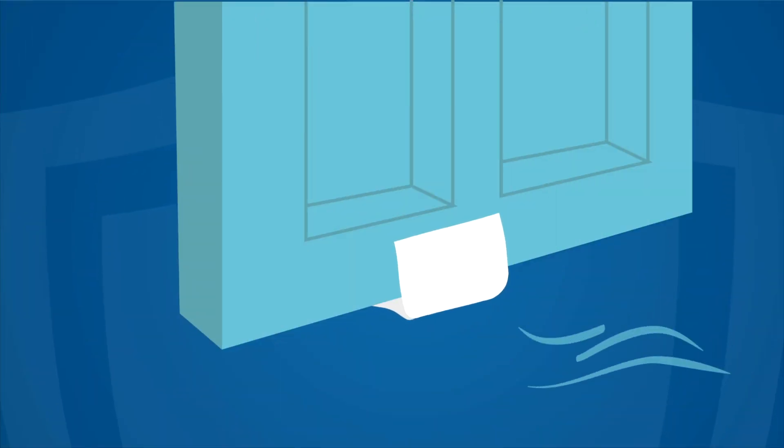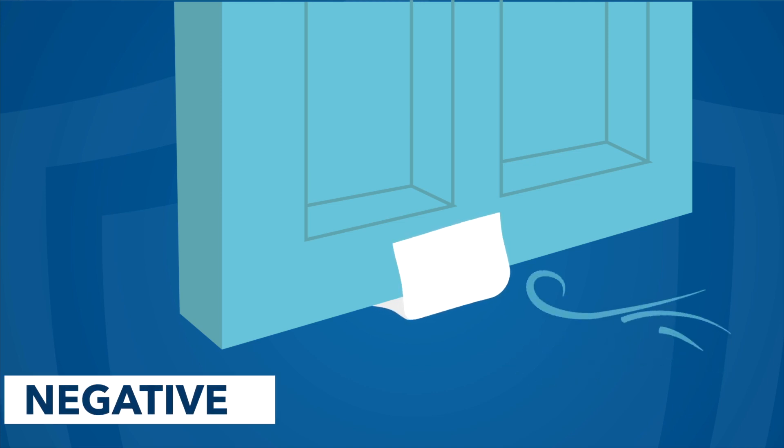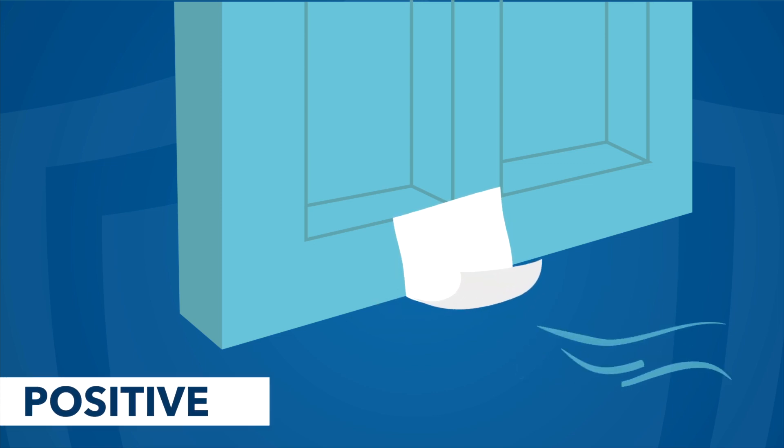If you are concerned about a room's pressure, you can quickly check to see if a room is positive or negative pressure by holding a tissue or piece of toilet paper at the bottom of the closed door. If the paper is sucking in, the room is negative. If the paper is blowing out, the room is positive.